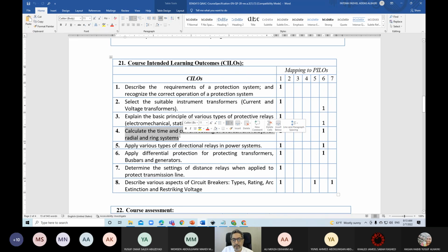Then we'll start covering the first and oldest principle of protection, which is based on overcurrent. When current exceeds a threshold, a limit, then we declare there is a fault or there is an overcurrent condition, and a relay trips the protected equipment, okay, at a set time. We'll focus on this chapter. How do we set the current settings at which you detect the faults, and the timing at which the relay trips the circuit breaker to disconnect the protected equipment or the faulty equipment.